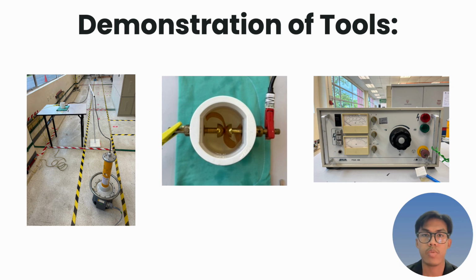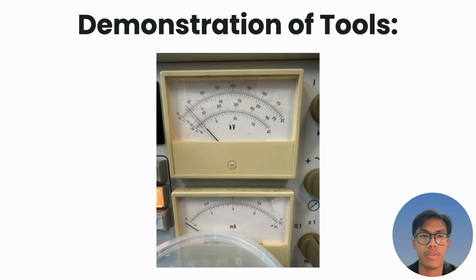The BDV test was conducted by submerging the paper in oil between the spherical electrodes. So the voltage was increased gradually until dielectric failure occurred. So the BDV were recorded to ensure the values are captured. So this is the example video of how BDV tests are recorded. The voltage was increased gradually and slowly until the breakdown occurred.